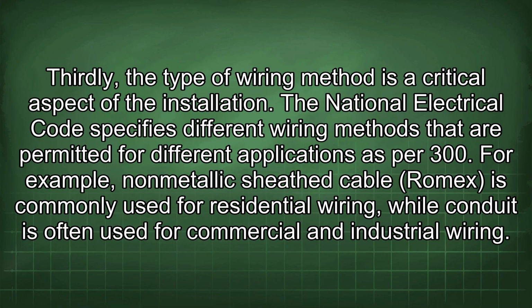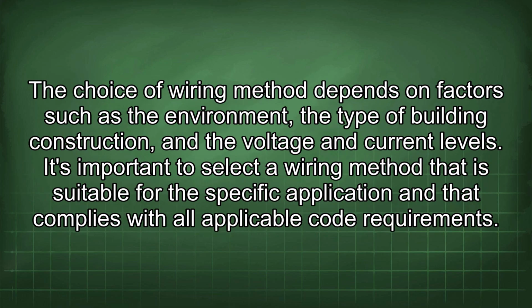Thirdly, the type of wiring method is a critical aspect of the installation. The National Electrical Code specifies different wiring methods that are permitted for different applications, as per 300. For example, non-metallic sheathed cable (Romex) is commonly used for residential wiring, while conduit is often used for commercial and industrial wiring. The choice of wiring method depends on factors such as the environment, the type of building construction, and the voltage and current levels. It's important to select a wiring method that is suitable for the specific application and that complies with all applicable code requirements.